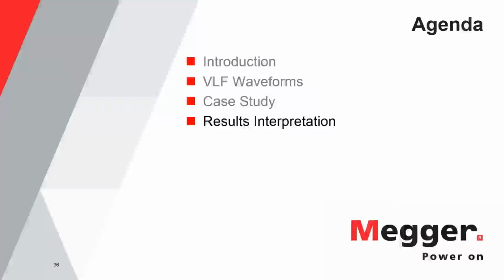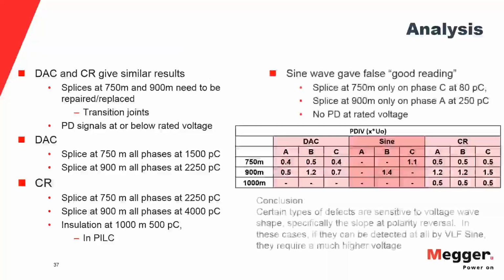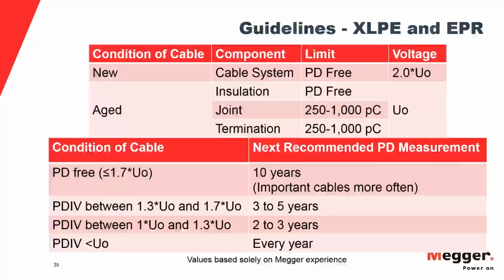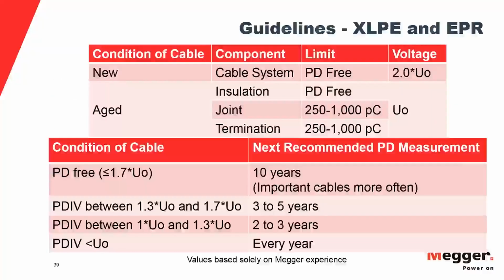They found some tracking and respliced, repaired, and then the PD activity in the cable is just a little bit more closely monitored, but it's not really a reason for concern. Again, in PILC, very low magnitude, not too crowded, not in one spot, and that was pretty much the outcome of that.